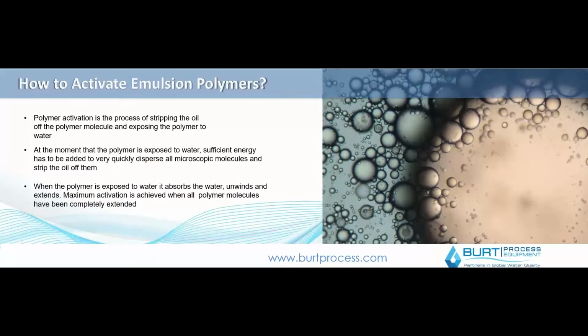The process of activation of an emulsion polymer involves stripping the oil off the polymer molecule and exposing the polymer to water. In most systems the polymer is used at fairly low concentrations. You generally don't use a lot of polymer, and anyone who's used polymer in the field, or even in a swimming pool, knows overdosing polymer is very bad because you end up with cloudy base water where the polymer is essentially floating in there. So you dilute it into a water stream, strip it of the oil, introduce it into that water stream, and then activate it. That's the process by which polymer systems work.